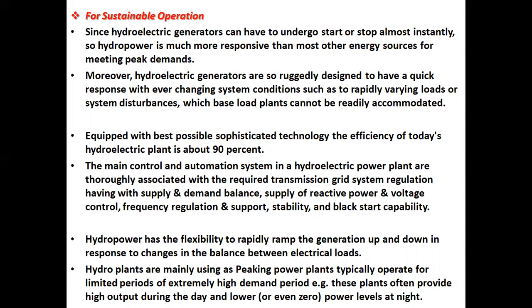Equipped with the best possible sophisticated technology, the efficiency of today's hydroelectric plant is about 90%. The main control and automation system in a hydroelectric power plant is thoroughly associated with the required transmission grid system regulation, having supply and demand balance, supply of reactive power and voltage control, frequency regulation and support, stability, and black start capability. Hydropower has the flexibility to rapidly ramp the generation up and down in response to changes in the balance between the electrical loads.